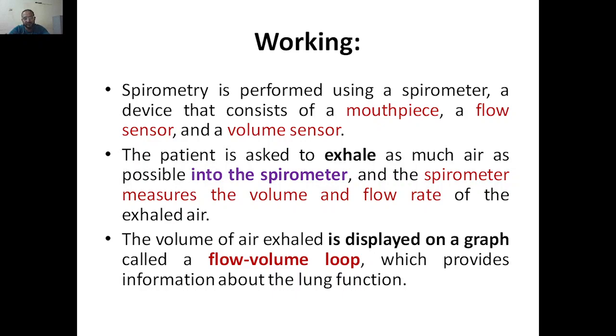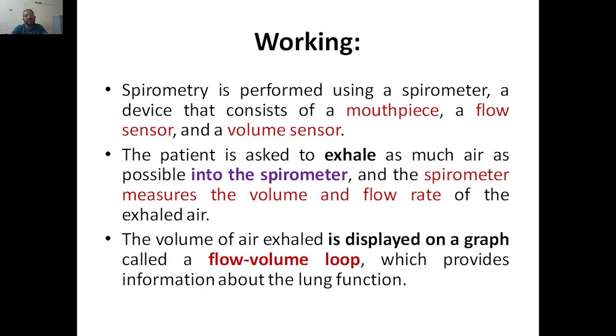The patient is asked to exhale. When you exhale through the mouthpiece, the volume sensor detects how much air is coming through, and the flow sensor detects the flow rate. From these two readings, the volume of air is displayed on a graph. The graph is plotted as a flow-volume loop, which provides information about the lung function.